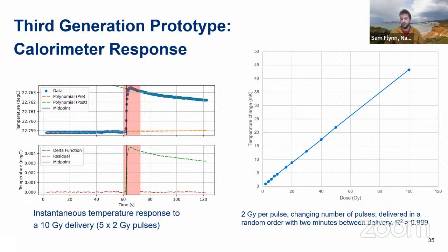We show that it's linear. This device is very, very linear. Again, showing a straight line is a straight line, but there's no reason it shouldn't be. It's linear up to 100 grays, and in theory, unless you start to get to the point of melting aluminium, no maximum. You can keep going as high with this. So if FLASH 2 were ever invented that delivers at gigagrays per second, this device could potentially be useful for it. This is obviously best case scenario though.